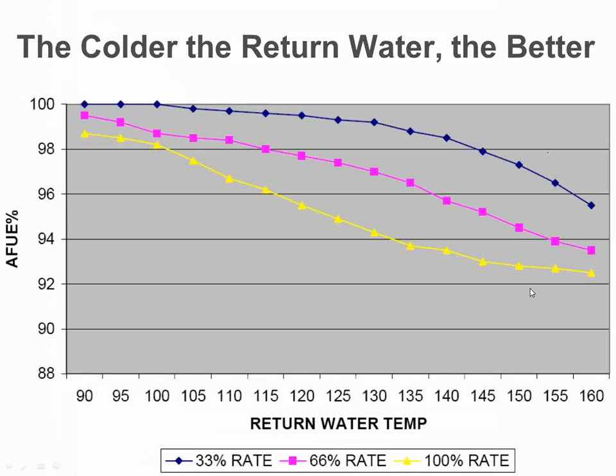But look at a more specific boiler, right? This is a boiler we had in our lab here in Melrose Park. And if you didn't know it, we have hands-on classes for all this kind of stuff. But this boiler with 160-degree return water at 100% fire is a 93% efficient boiler. It's a very nice mid-tier condensing boiler. And if I ask it for cooler and cooler water, it gets more and more efficient. When I get to 130, it does spike up a little bit. Not as dramatic as the regular boiler because it's already really efficient, but it does spike up at a bit of a faster pace.